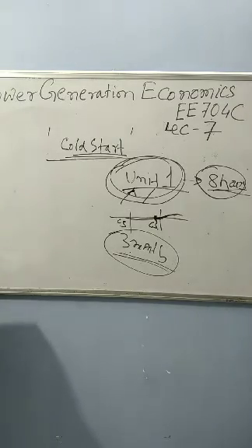So we have to see the first approach: cooling allows the unit boiler to cool down and then heat back up to the operating temperature in time for a scheduled turn on. Another approach requires that sufficient energy be input to the boiler to just maintain the operating temperature.